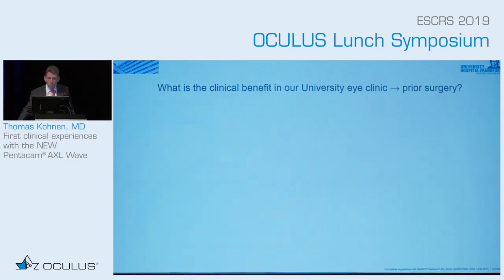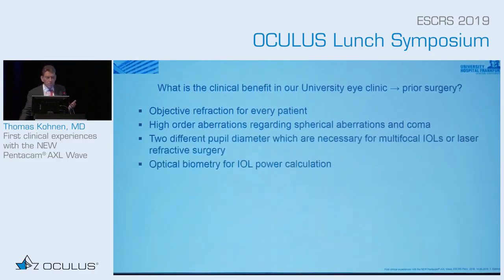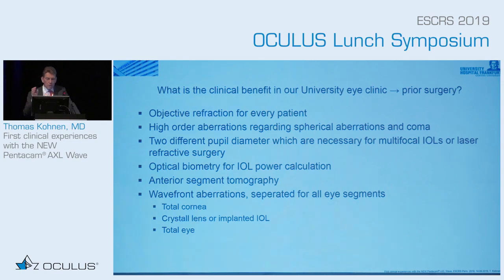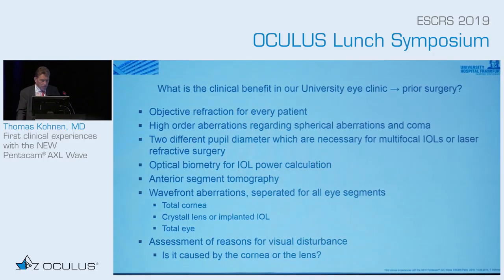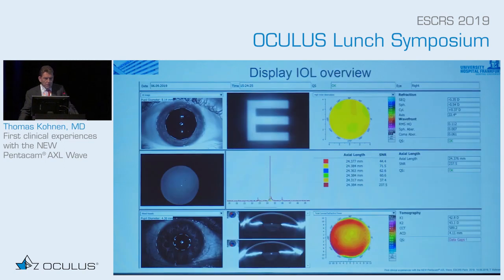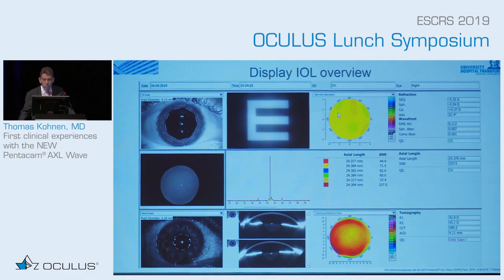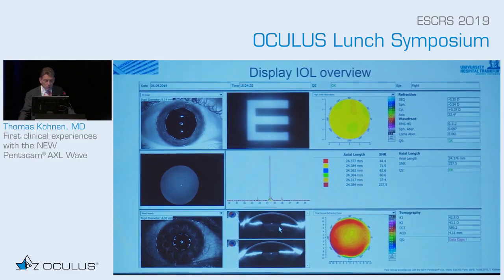For patients prior to surgery, what can we do? Objective refraction, high-order aberrations at two different pupil diameters, optical biometry for IOL calculation, anterior segment tomography, and wavefront aberrations with the total cornea, crystalline lens or implanted IOL, and the total eye. You have all these measurements on one display: the retroillumination, aberration measurement, total corneal refractive power, refraction, axial length, anterior tomography, and pupil size.